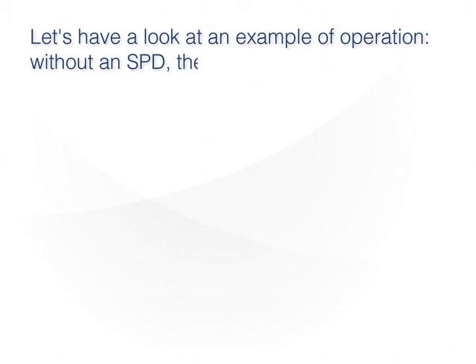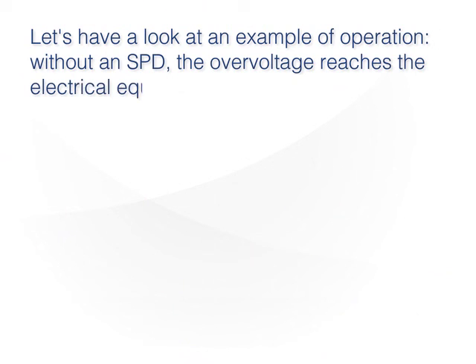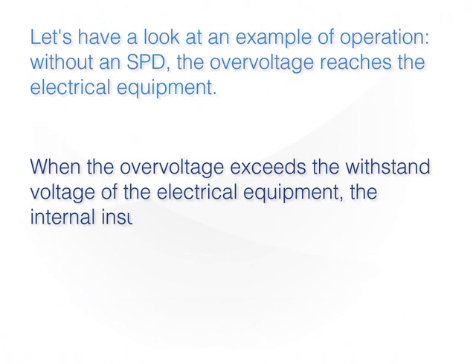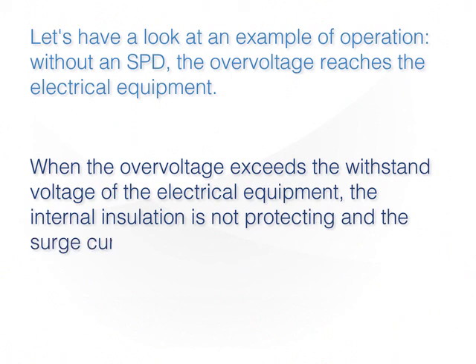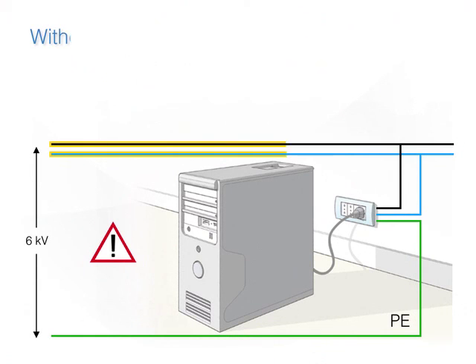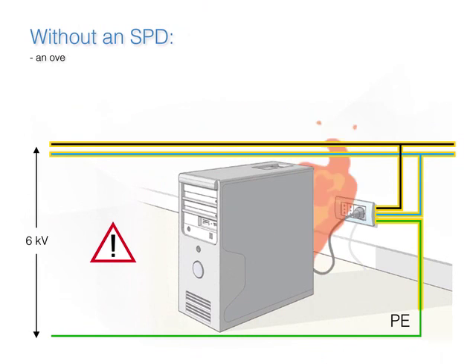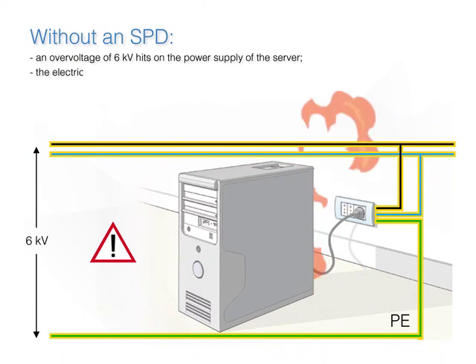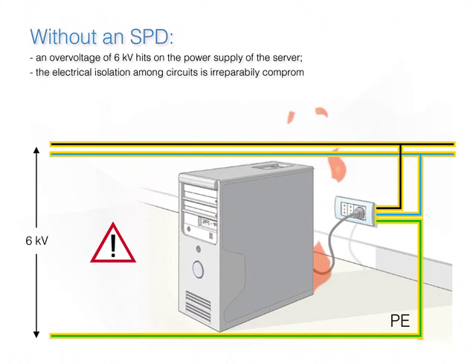Without an SPD, the overvoltage reaches the electrical equipment. When the overvoltage exceeds the withstand voltage of the electrical equipment, the internal insulation is not protecting and the surge current destroys the equipment. Without an SPD, an overvoltage of 6 kV hits the power supply of the server. The electrical isolation among circuits is irreparably compromised, and a discharge to ground is generated.